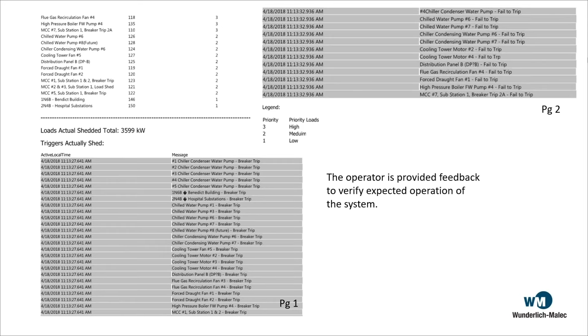So look at that. With the system that Chris described, we've kept all the load running as much as we could. You might have lost a single pump, but the rest of the plant is 100% stable. The operator can watch the plant and change those priorities on a day-to-day or seasonal basis, and see from that report that the system worked exactly as intended.